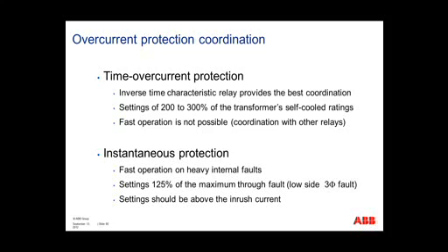For time overcurrent protection, an inverse time characteristic relay provides the best coordination, especially with other relays downstream. Settings of 200 to 300% of the transformer self-cool ratings are typically used. Fast operation is not possible, because these time overcurrent relays need to be coordinated with other relays downstream.